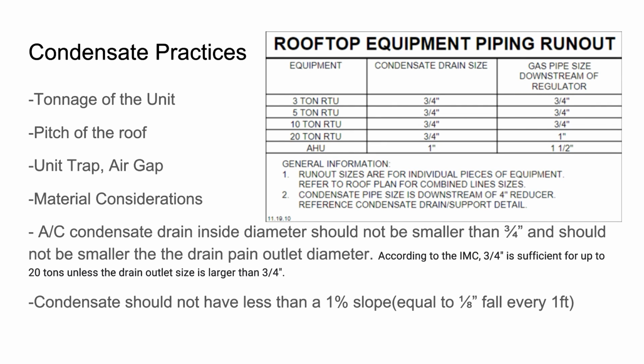Condensate practices. Dan is much more familiar with this than me. So when we're doing commercial applications, most of the time everything we have is pre-engineered. They tell us what we have to use. If you're tying multiple units into the same run, that does dictate what size you're going to be running. So if you have two 20 tons running down the same pipe, you still can't go with a 3/4 inch drain line. You actually have to accommodate for both of those lines to be draining at the same time.